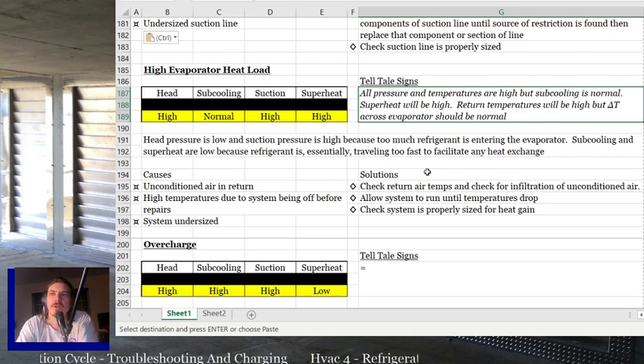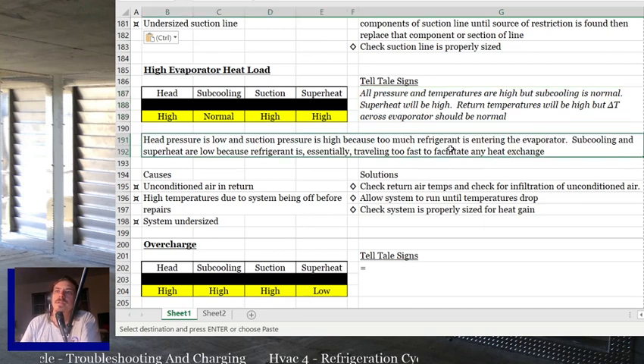The telltale signs are all pressures and temperatures are high, but subcooling is normal. Superheat will be high. Return temperatures will be high, but delta T across the evaporator should be normal. So if it's 80 degrees inside and you got a 60-degree supply, you got a 20-degree delta, it's working. Well, the question is why is the return 80 degrees? Is it just a high heat load? The system's been off? Is there some other problem? So the head pressures, oh, see, I didn't write this one out. I need to write that one out.